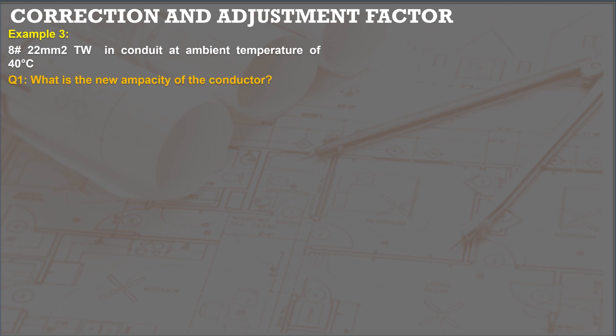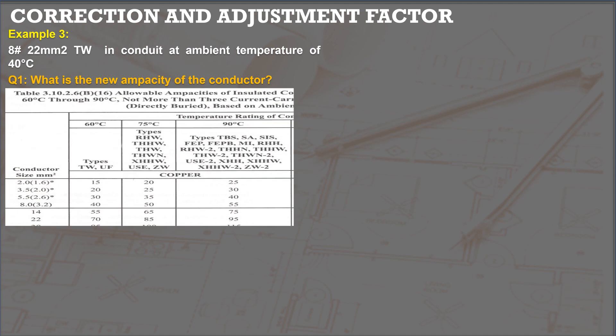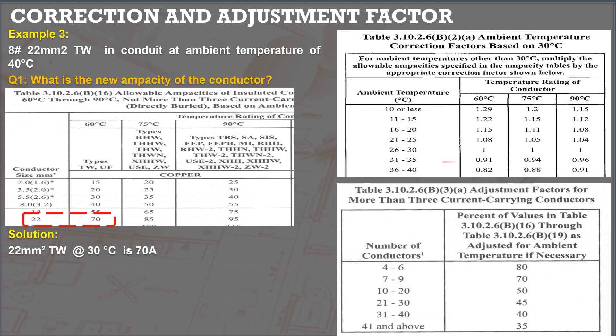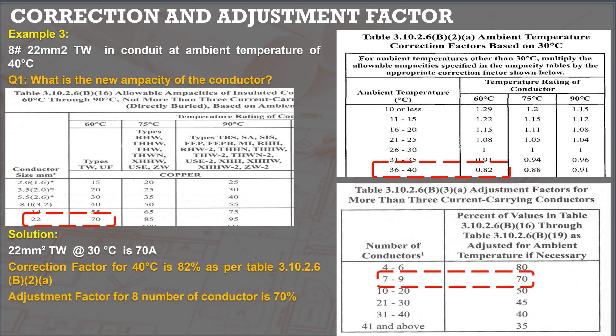Let's have another example. Eight 22 squared millimeters TW are installed in one conduit with an ambient temperature of 40 degrees Celsius. As per Table 3.10.2.6 B16, the ampacity of 22 squared millimeters TW is 70 amperes. The correction factor for 40 degrees Celsius is 82%, and the adjustment factor for seven to nine conductors is 70%. Therefore, the new ampacity of 22 squared millimeters shall be 70 × 82% × 70% = 40.18 amperes.